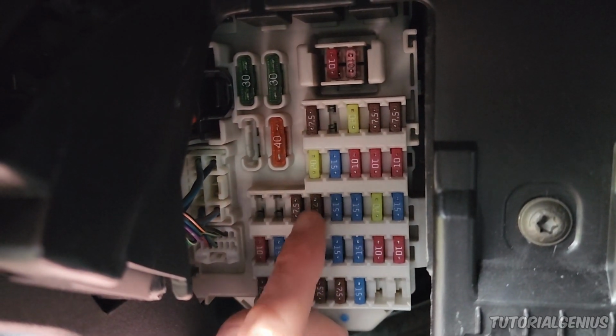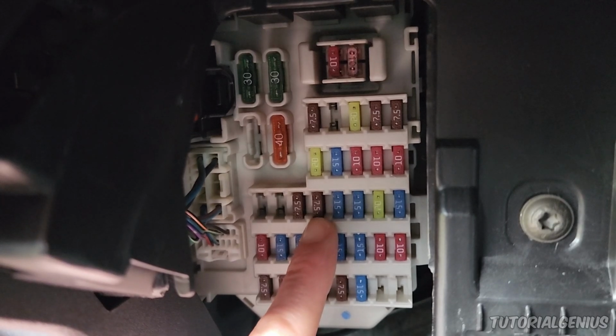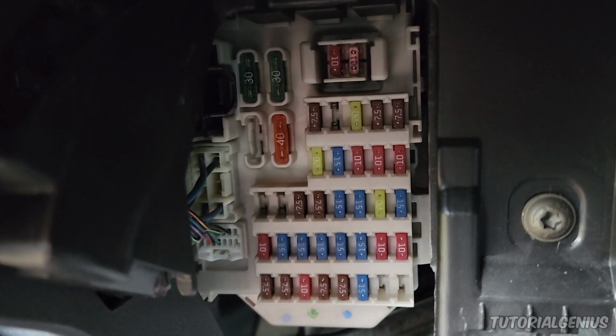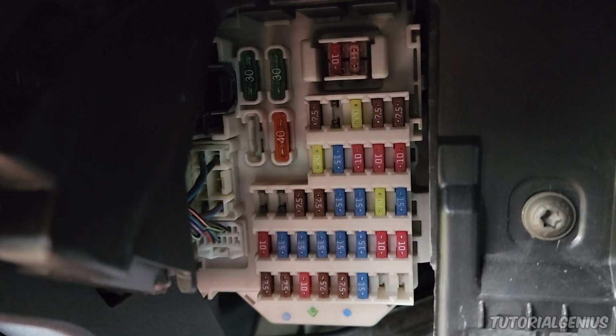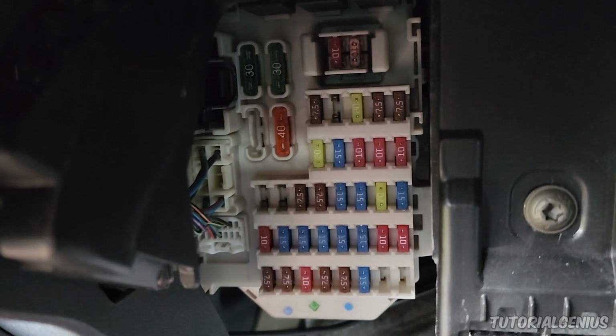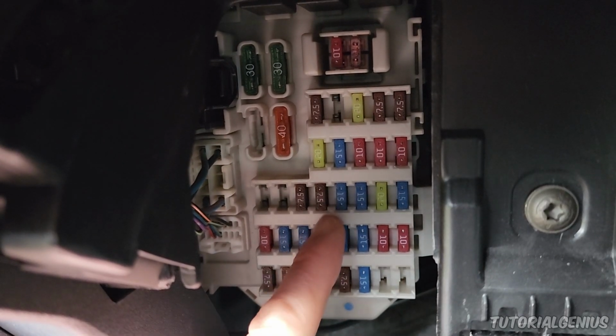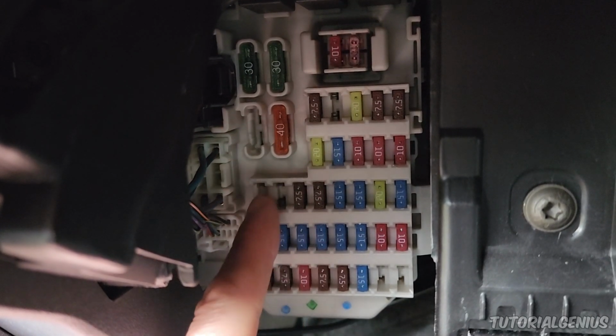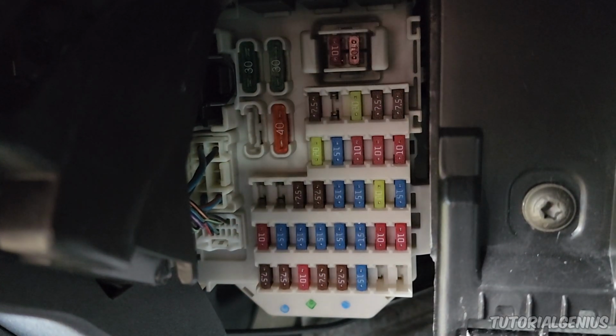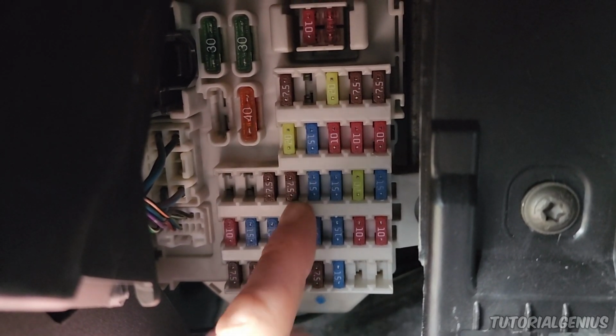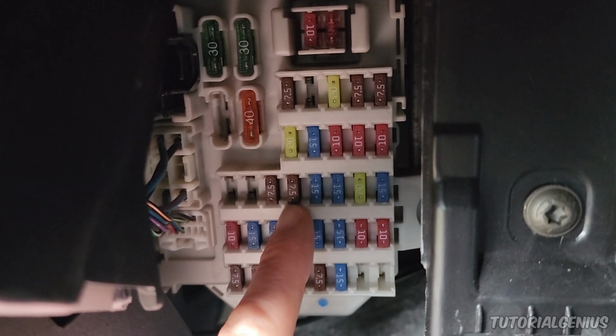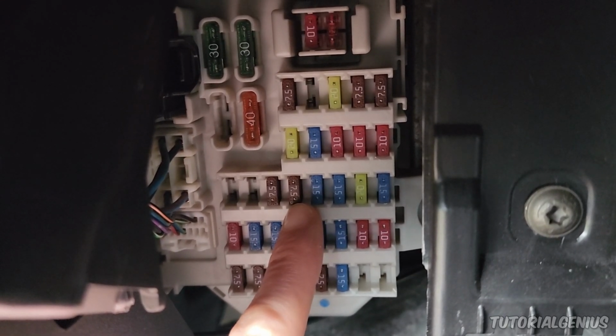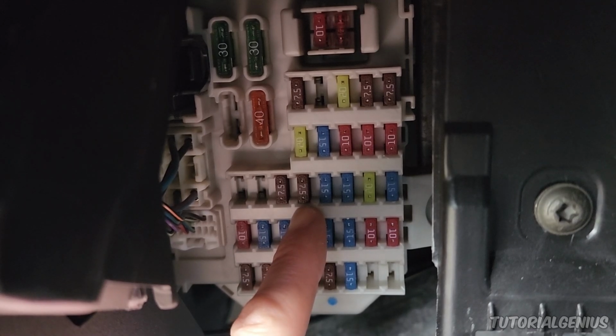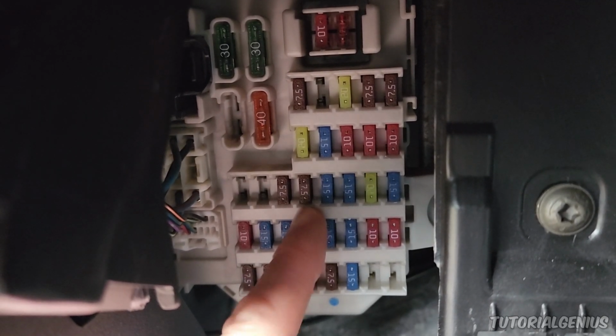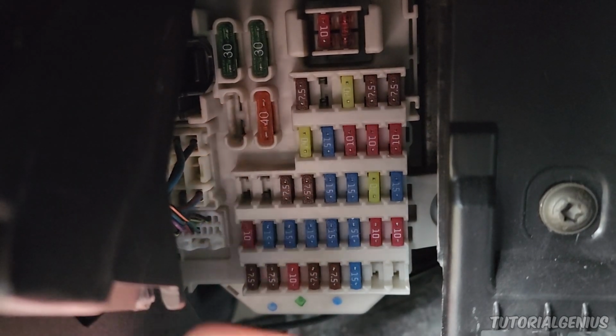Let's say this 7.5 amp fuse has appropriately sized wiring for something running at 7.5 amps, maybe the gauge of wiring is good for 10 amps of current. If we're piggybacking this 7.5 amp fuse with another circuit, also drawing 7.5 amps, each sharing the same positive wire rated for 10 amps, and both are drawing maximum current, we could be running 15 amps through a wire that's only gauged for 10 amps.